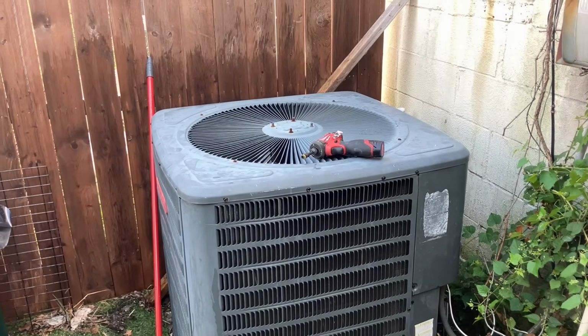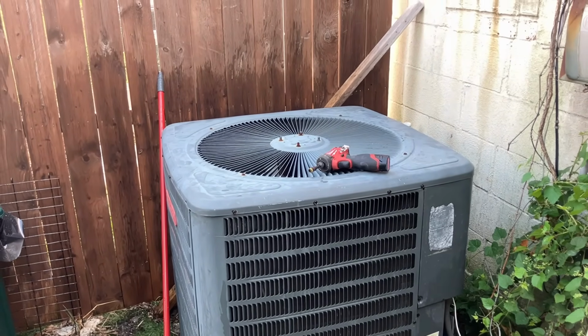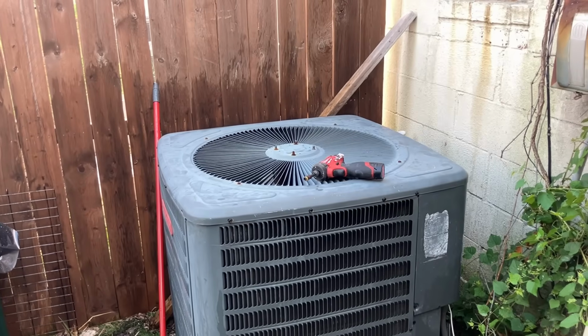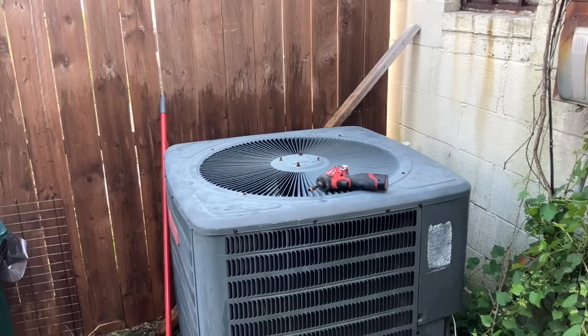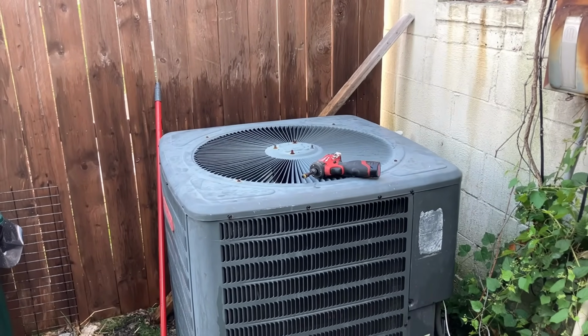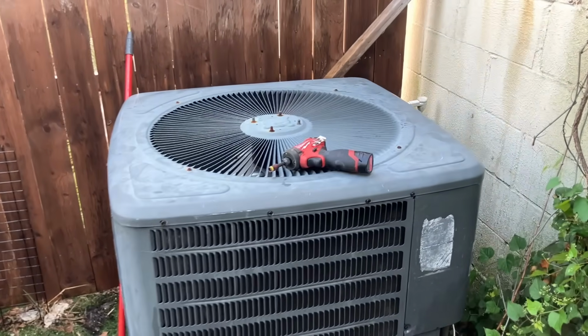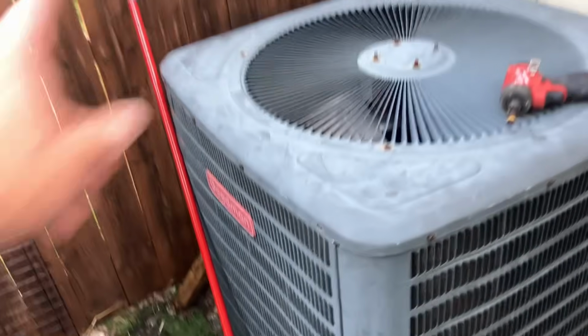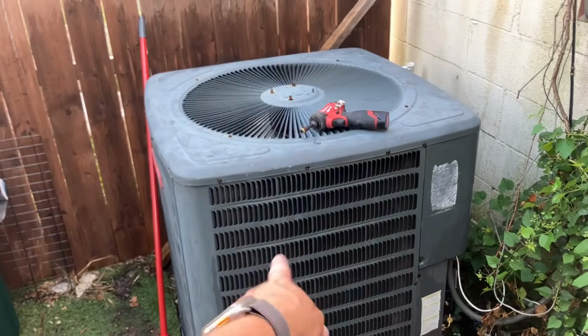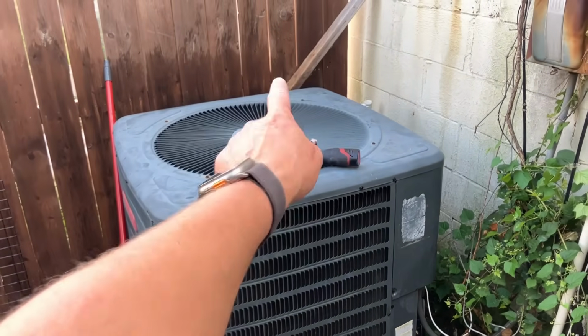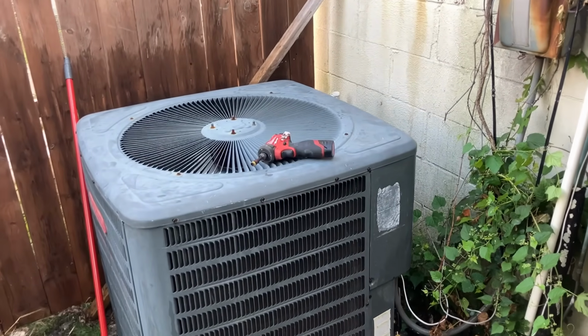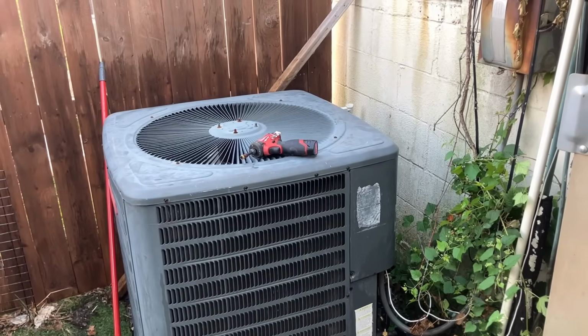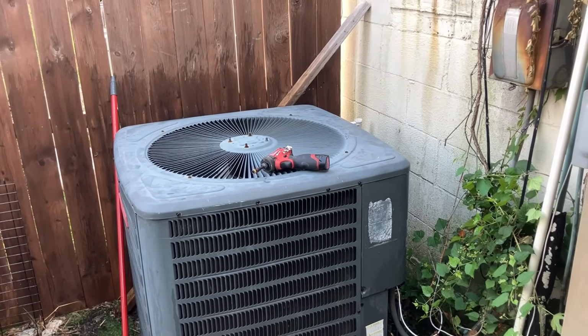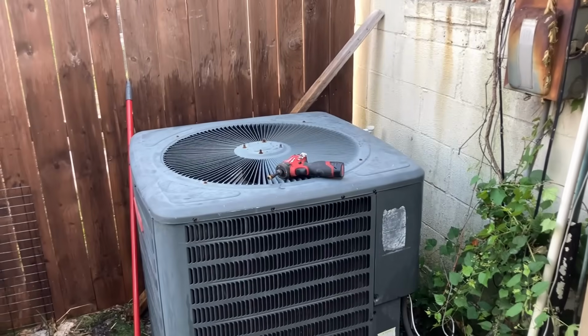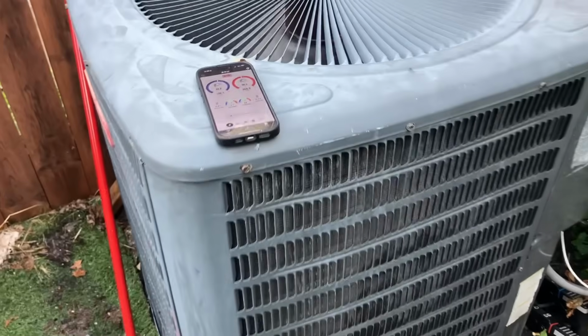All right, I decided to spare you guys all the drama on getting the condenser fan motor shroud assembly back on top of the unit. You know it's not easy, folks. And in the process, I also lost a screw. All the other screws are in though. Compressor is a 45, fan is a 5. Let's fire this up and we're gonna dynamically test the dual capacitor, making sure it's within range while the system is running. So stick around, folks.